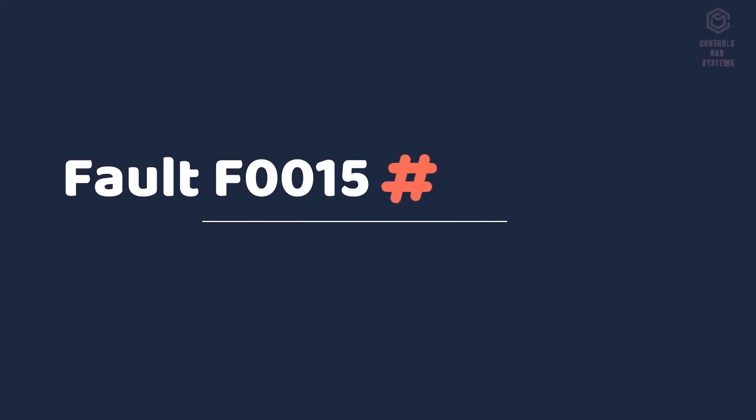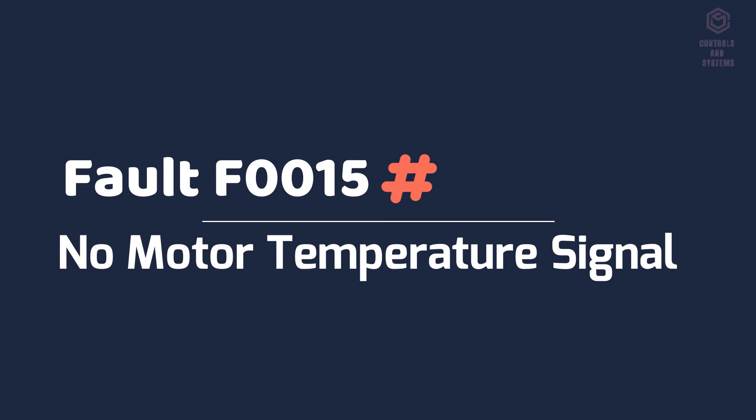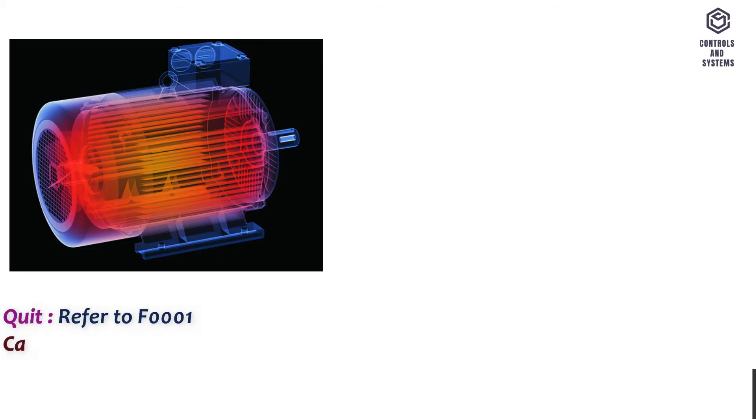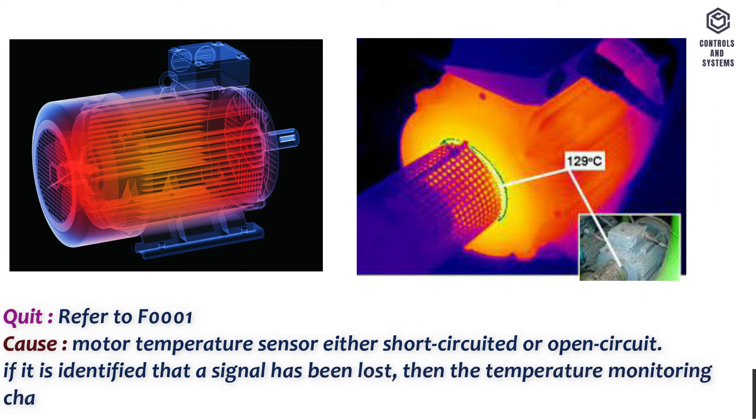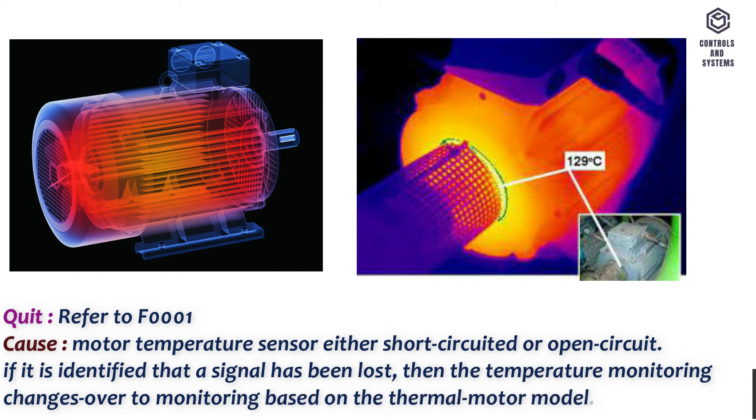Fault F0015 no motor temperature signal. Quit: Refer to F0001. Cause: Motor temperature sensor either short-circuited or open-circuit. If it is identified that a signal has been lost, then the temperature monitoring changes over to monitoring based on the thermal motor model.